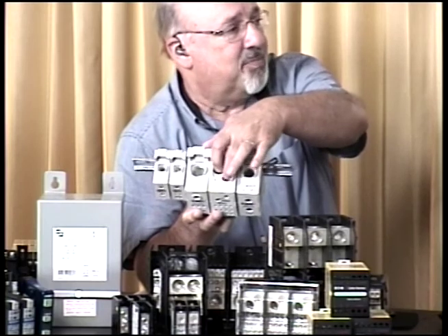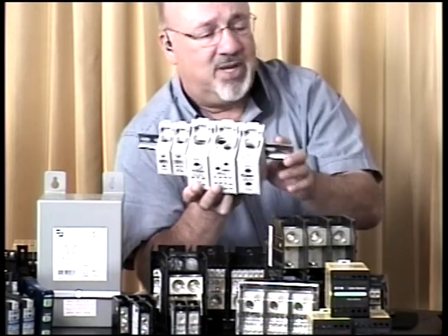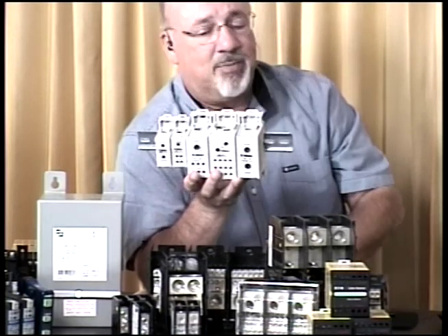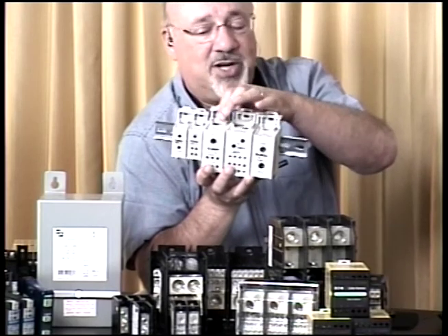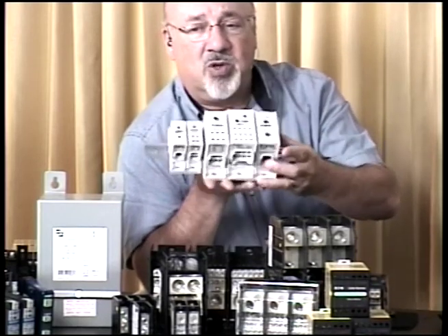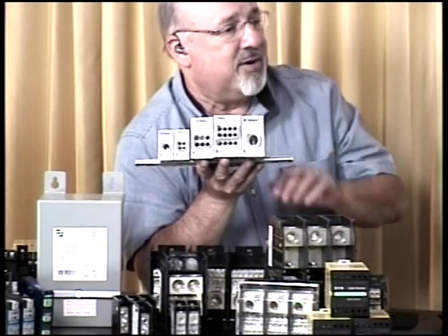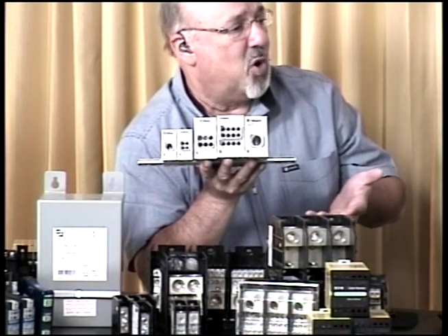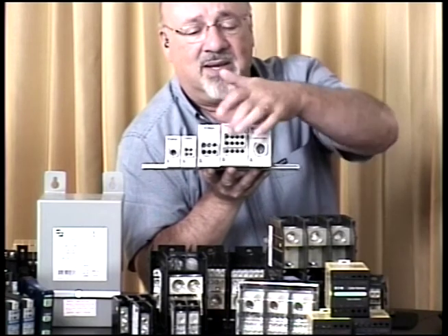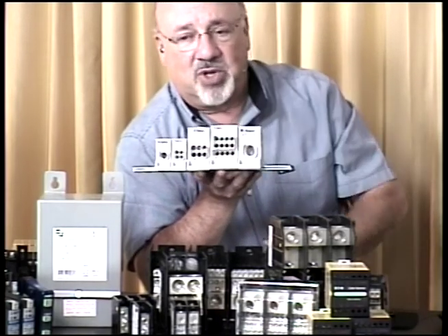It could be something in the neighborhood of 2-aught, which would be 1 inch in diameter with the insulation on it. And from there, you want to distribute it to something like 10 gauge wire that goes out to different transformers, motor starters, and that would come off the bottom.